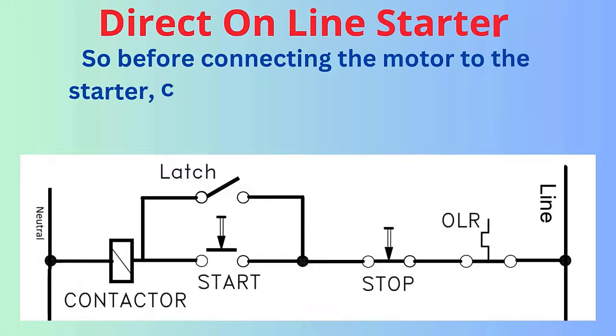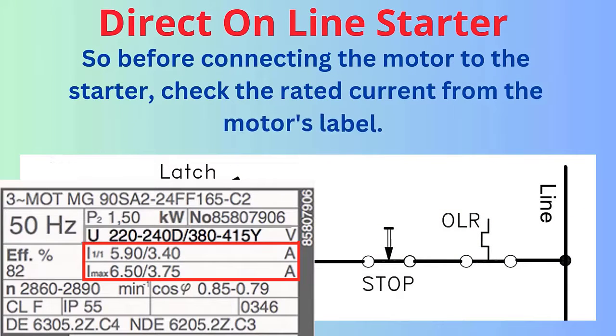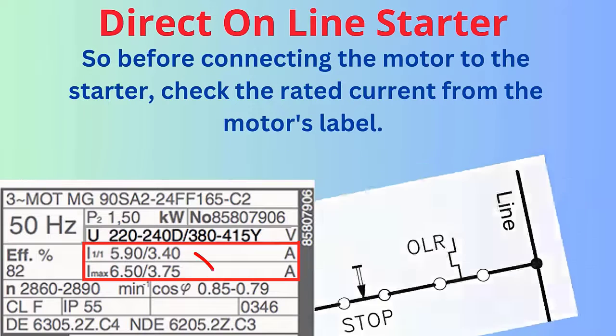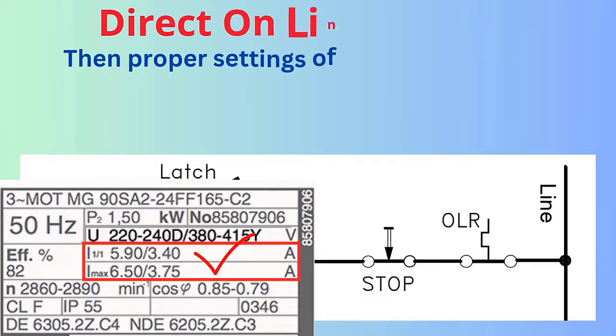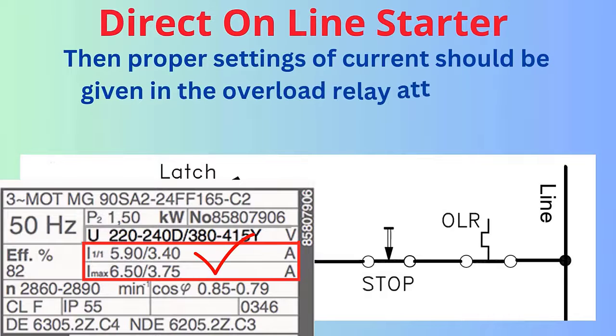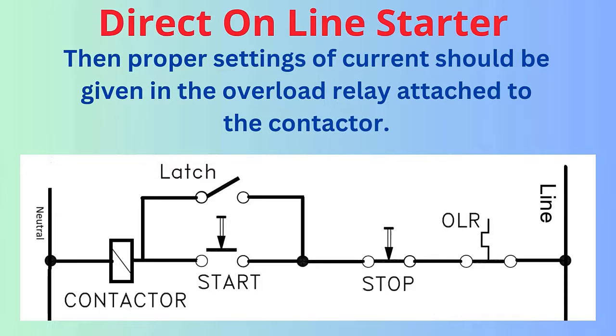So, before connecting the motor to the starter, check the rated current from the motor's label. Then, proper settings of current should be given in the overload relay attached to the contactor.